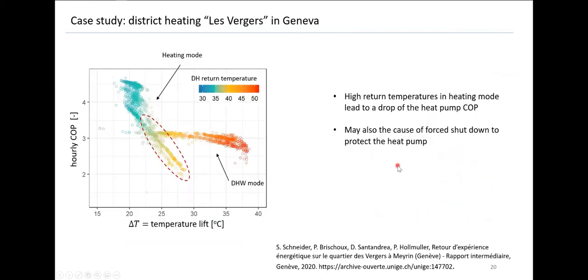One particularity of this district heating network is that it has two operating modes. During heating mode, the supply temperature is set to 50 degrees. Twice a day it switches to a domestic hot water mode for two hours, where the supply temperature is set up to 65 degrees to heat up the domestic hot water buffers in the buildings. The COP graph shows that in heating mode the return temperature is critical — higher return temperature means a higher temperature lift on the evaporator, a much lower COP, higher electricity demand, and sometimes the heat pump must be shut down for protection.